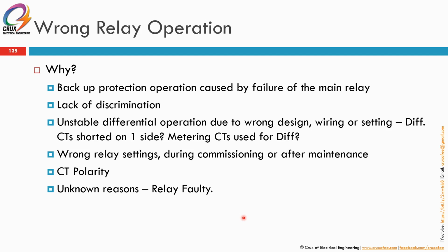But if there's a batch defect, normally you can see the batch defect problem within 1 year or 2 years. So if you have a lot of relays in your batch, for example if you upgrade 100 relay units and 2 or 3% of the relays are faulty due to internal memory or internal card problems, you should go into further detail and ask the OEM to issue a batch defect, so that maybe you will be required to replace those faulty units or maybe the whole batch. Normally the OEM, if they receive at least about 2 to 3% worldwide problems on the relay, will recall that relay.